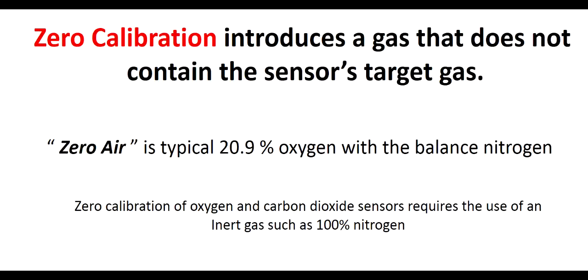Zero calibration introduces a gas that does not contain the sensor's target gas. It is used to give the sensor a clean atmosphere reference point. Zero air is typically 20.9% oxygen with a balance nitrogen. Zero calibration of oxygen and carbon dioxide sensors requires the use of an inert gas such as 100% nitrogen.